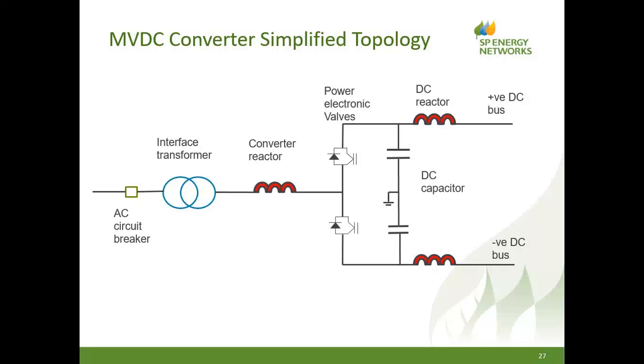As it turns out, because the DC voltage is essentially the peak of a 33 kV sine wave, this interface transformer is more or less a 1-to-1 ratio transformer. It would normally be a star delta transformer, just as would be normal. The heart of the technology is the power electronic valves. Here I've shown the symbol for an IGBT, and as I mentioned before, the DC capacitor is the transitory storage of energy. So having charged the DC capacitor up, we can invert that DC capacitor voltage through the power electronic valves to create a sinusoidal waveform at the secondary of the transformer.